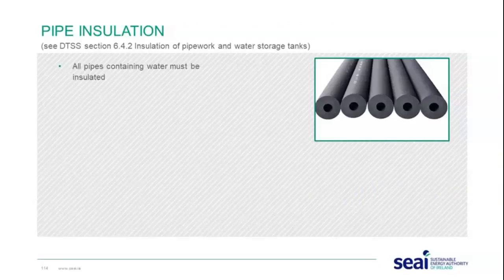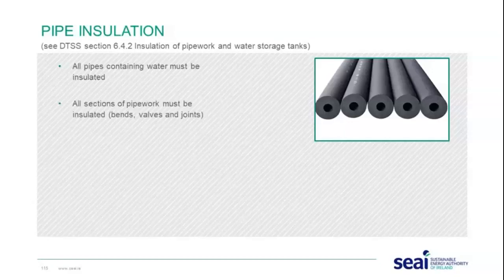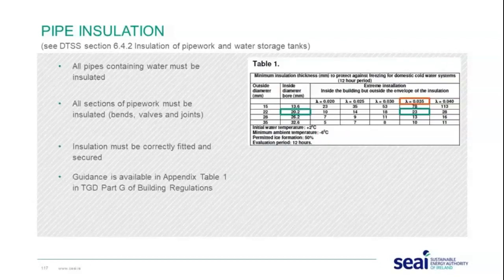Regarding pipe insulation — refer to the Domestic Technical Standards and Specifications section 6.4.2. In an attic, all pipes containing water must be insulated. All sections of pipework must be insulated, including any bends, valves, and joints. Insulation must be correctly fitted and secured. Further guidance is available in Appendix Table 1 of Part G of the Building Regulations.